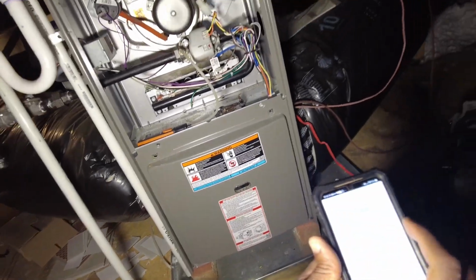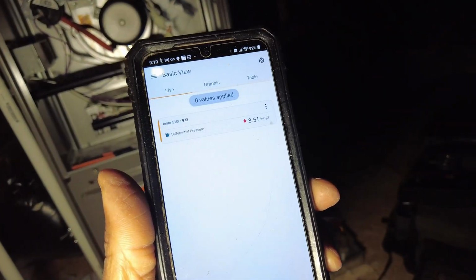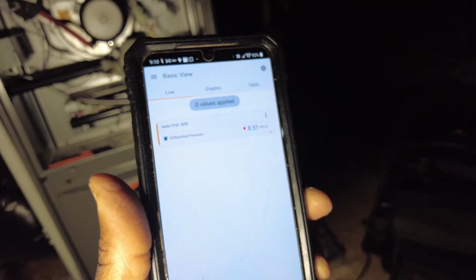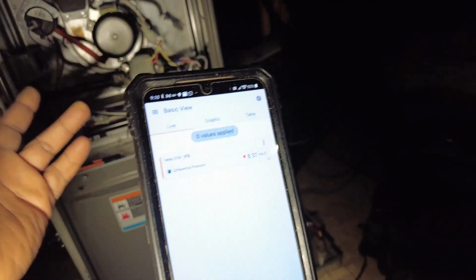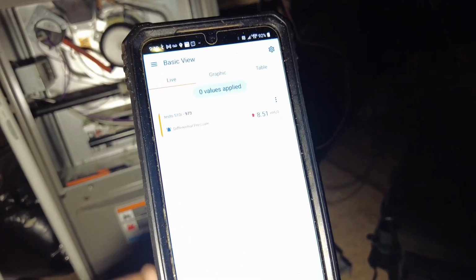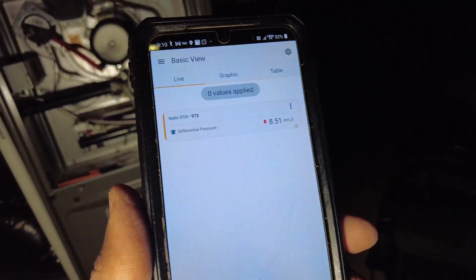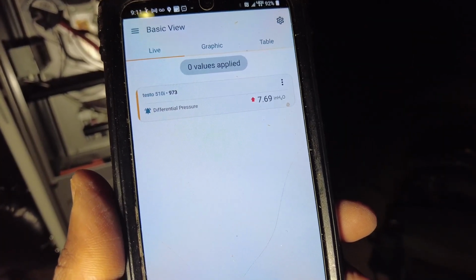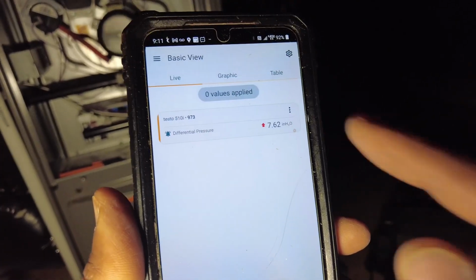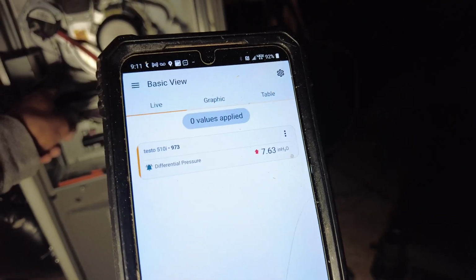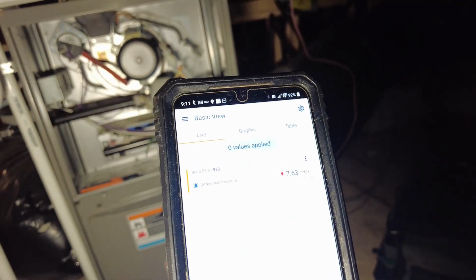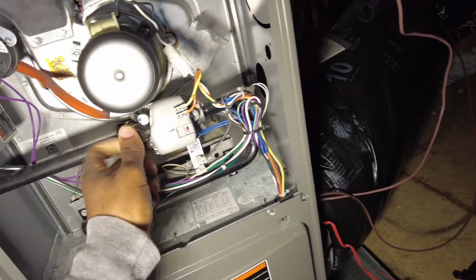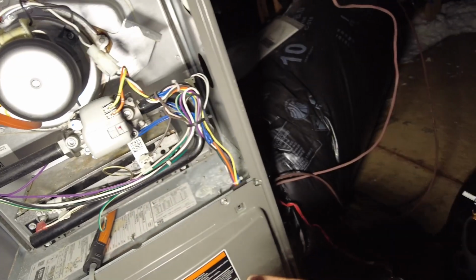All right, so you're going to see this gas pressure drop as well. So that's so crazy. So essentially, it's right now 8.5. By the time the gas valve opens up, it's going to probably drop down to about 7.8, something to that effect. So there you go. And that's because the pressure on the line before was static. Now it's flow. That's flow pressure that you're seeing now. So it's always going to be a little less. Okay. So we'll go ahead and capture that. You don't want to over tighten these, because that's just an aluminum body. You know what I mean, on the gas valve. So just snug it up.